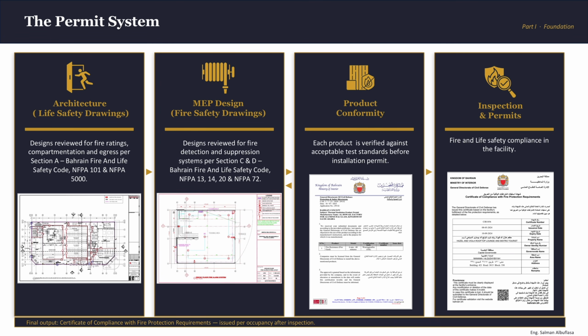And this takes us to inspection and permits. Basically, any engineer can walk through a building and verify that what is installed exactly matches the layout. You'll walk with the layout, you'll just match exactly what is on the ceiling and what's on the wall with the layout. It doesn't take much effort, it doesn't take much experience. But a fire inspector does more than that, or should do more than that. The fire inspector has the eye to evaluate the premises for hazards: the blocked exit, the flammable materials, the electrical issues, different fire loads. They test fire protection systems or oversee the testing, and they verify the product and they identify hazards that were never on any drawing, because they were never supposed to be there in the first place. The layout examiner might not see everything in the building, but the fire inspector sees everything in that building. He's the eye of the plan examiner.